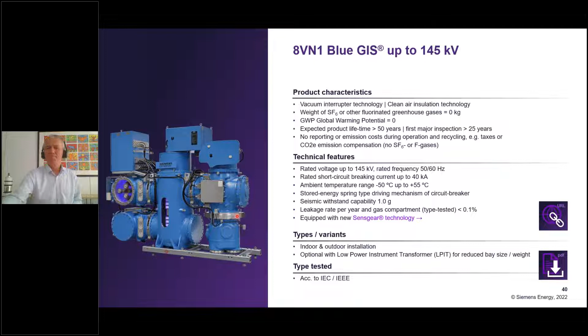So as I said, clean air has lower dielectric strength than SF6. So how to compensate that? There are 2 ways to compensate. One is to have a bigger distance between the conductor and the housing, and the second, higher pressure. So we combined that. We increased the pressure from 6 bar to around 8 bar in that blue technology, and we used bigger housings. But what does that mean, bigger housings?